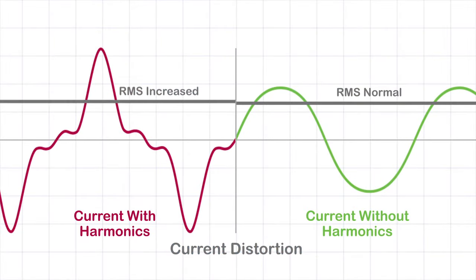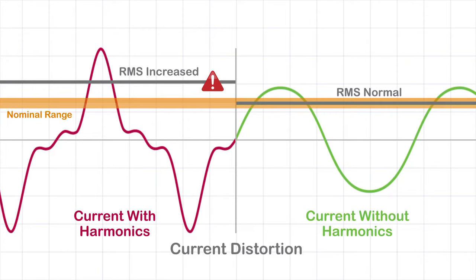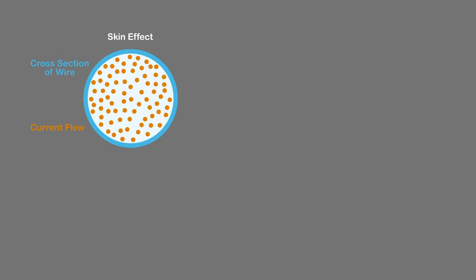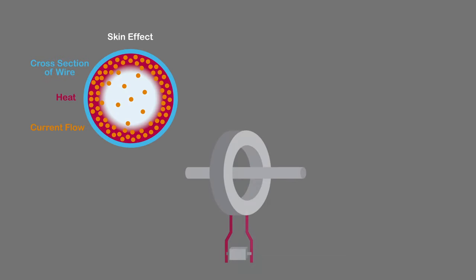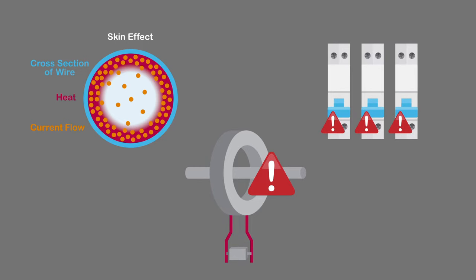Current distortion increases the electrical distribution network RMS current that can cause skin effect on a conductor, overload transformers, and nuisance tripping of circuit breakers.